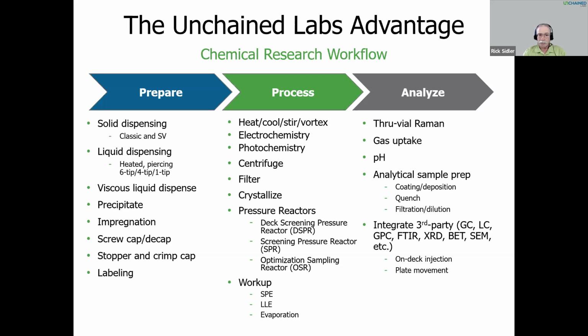And we can even include on-deck injectors and injector ports to facilitate that. We can prepare plates of samples and move those, either automated or manually move those into integrated LC instruments. And to facilitate these analyses, we can do a variety of different sample prep manipulations there, whether it's quenching reactions, diluting them, filtering them, getting them into different solvent systems.